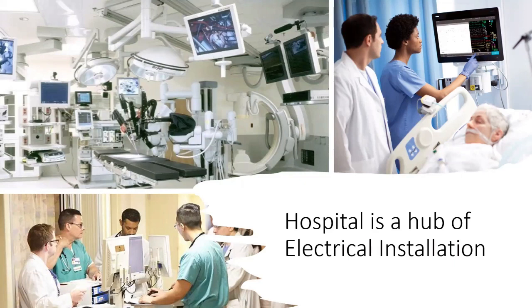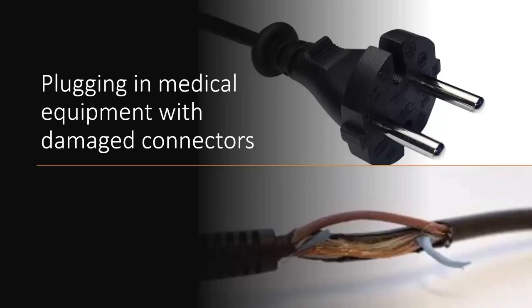That means the staff, patients, the doctors, or everyone in the vicinity of the machines or the electrical connection are in constant contact with an energized equipment or a conductor. If it's not properly handled, it can be really dangerous or fatal to any or all of them in case an accident happens. These dangerous situations can be due to sheer negligence. For example, plugging in an equipment with a damaged connector or a frayed wire, or plugging in an equipment or a connector without a third pin, the earthing pin. All of these will result in a no-earth situation, which means some shock can happen.